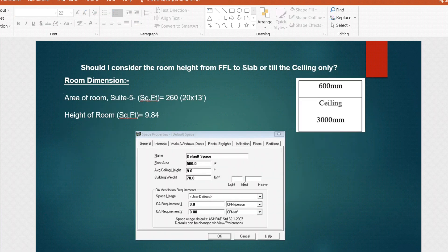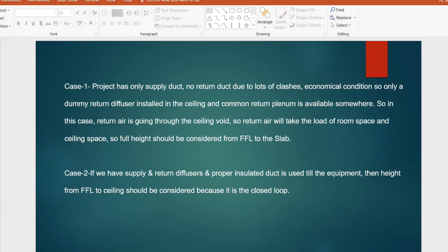The next question, also related to HAP cooling load calculation: the space shows an average ceiling height of 9 feet. If in the room section there is 3000 mm from bottom slab to ceiling and 600 mm between the ceiling void, when entering the height should I include just 3000 mm or the full 3600 mm? There are two cases to study.